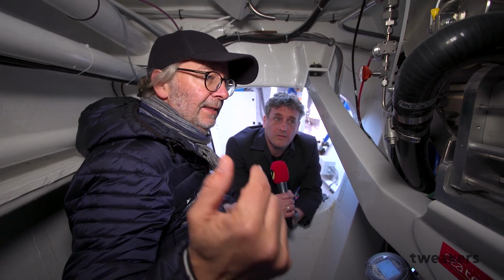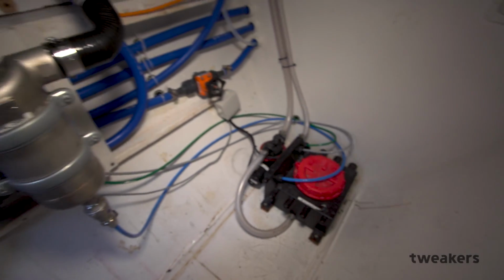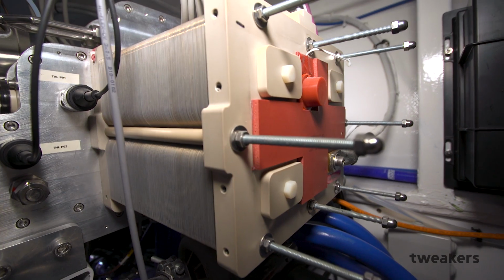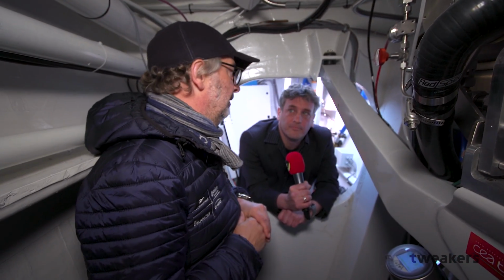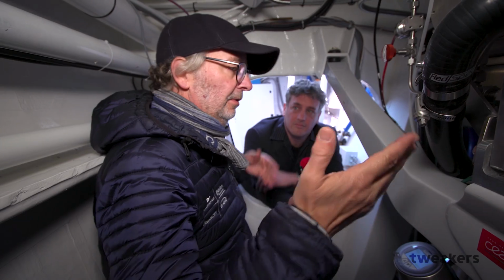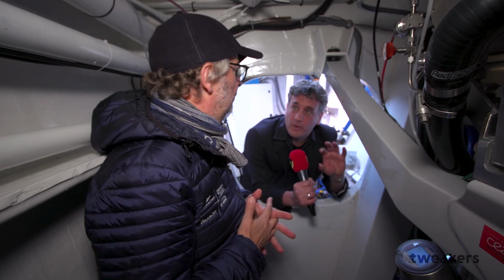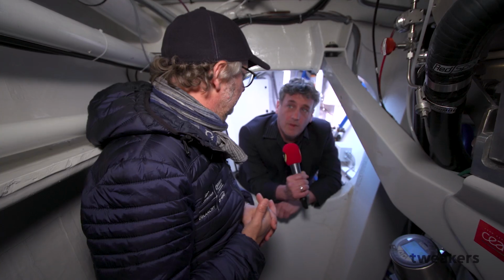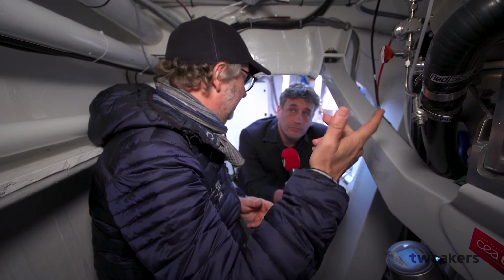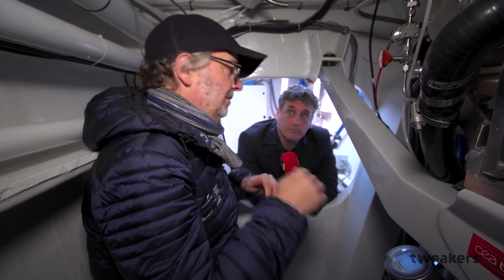Okay. So this zone is kind of protected because it is an ATEX zone, and there is a very strictly controlled atmosphere, humidity, pressure. So that's an ATEX zone. So we cannot open it when the fuel cell is working, even if it is not so dangerous. There is no danger at all. But when it's working, there aren't any people allowed here. No, for norms reasons. Oh, for norms, okay. You know, because there is no leak, absolutely no leak. As soon as there is a single leak of air, oxygen, or hydrogen, or whatever, the system just stops.